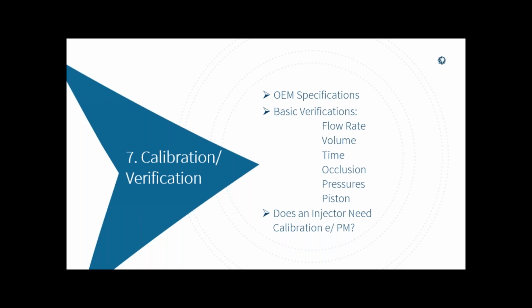Who does imaging? 80 kV is 80 kV, right? If it falls within specs, are you going to recalibrate it to make sure it's even closer to specs? No, if it falls within specs, you move on. Companies like to call their PM a calibration. Oh, we calibrate it all the time. Every time they come in, we calibrate the system. No, they don't. When you schedule your PM, you say, I'm going to need 2 hours. Oh, well, it only needs an hour. Okay. Just saying.